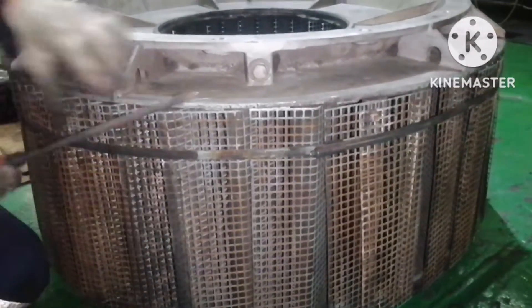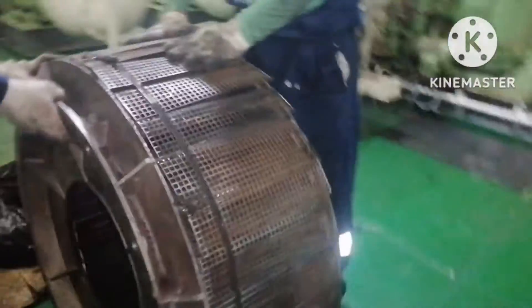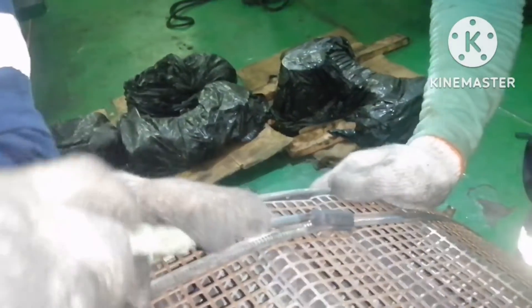The main thing to notice while boxing back the silencer filter is you have to inspect all the filter pads — that means all the filters and covers should be cleaned. I believe you must have got some information about how to assemble the generator turbocharger filter on board ships. The second clip is now fitted in place — you can see all the filters are in the silencer chamber. Both clips are in place; we are done assembling the generator turbocharger silencer filter. Thanks for watching, keep supporting, thank you all.